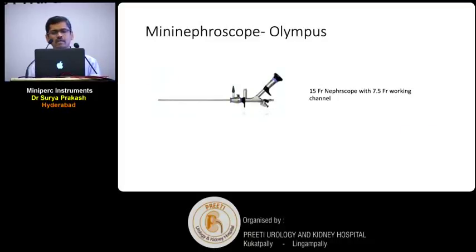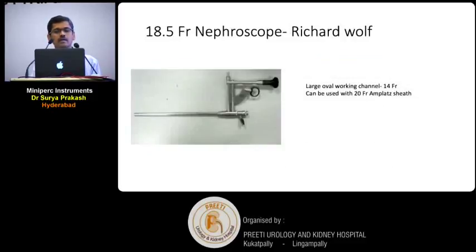Different companies have come up with their own solutions. Olympus has come with a 15 French nephroscope with a 7.5 French working channel. Richard Wolf has a 12 French nephroscope with two sheath sizes — 15 French and 18 French — suitable for mini-PCNL. The most commonly used in my practice for mini-PCNL is the Richard Wolf 18.5 French nephroscope without any outer sheath. It has a very large working channel of 14 French and can be easily used with a 20 French Amplatz sheath.